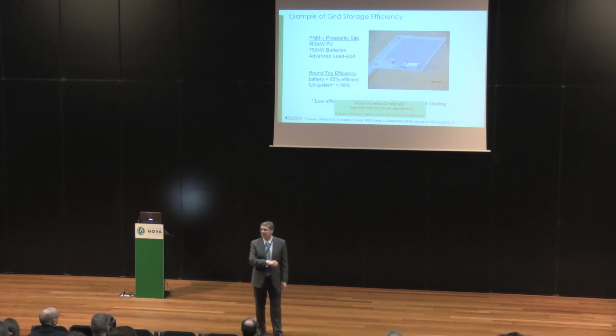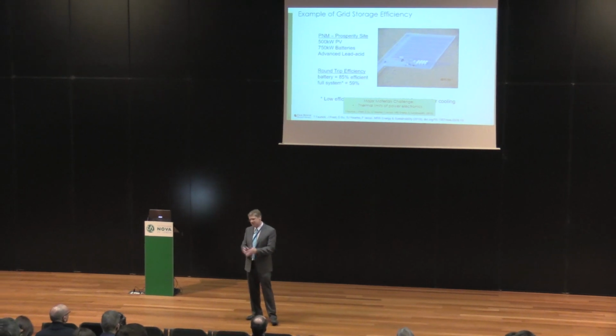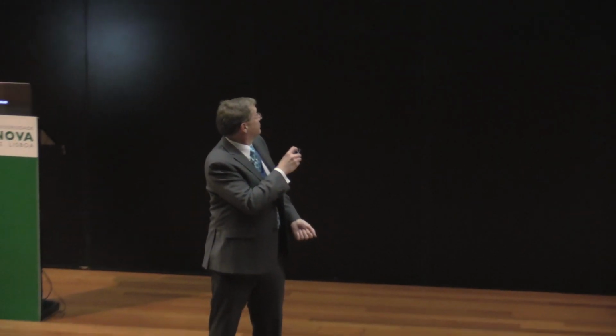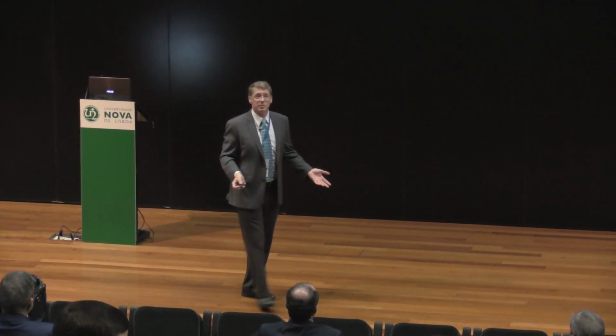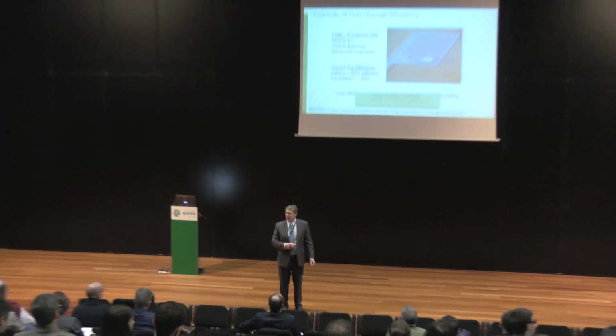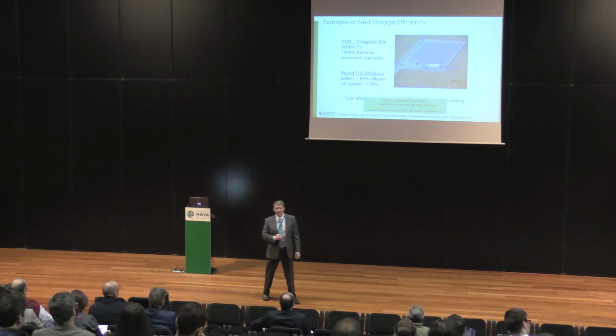However, as you go to wide bandgap power electronics, they have an advantage of the wider bandgap, meaning you need less of the actual transistors for doing in the system, but they also tend to be able to run at a hotter temperature. If you can push the operating temperature of the power electronics up to 200 degrees C, you now enable the use of passive radiators for cooling these power electronics, so you can get rid of this drop in efficiency due to the HVAC system. That's another opportunity for us to be looking at as a community. Obviously there are many people looking at power electronics, but I just want to encourage people to think about operating temperature and being able to drive that up higher.